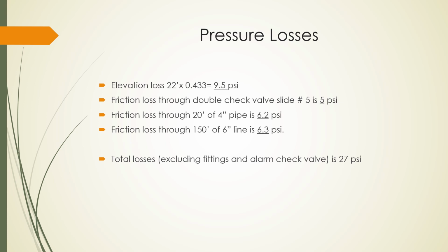The alarm check valve is generally good for 2 or 3 PSI. I'm just ignoring it here. The fittings would result in some loss as well. So excluding that, just not to complicate matters, we've lost about 27, but probably closer to 30 PSI.